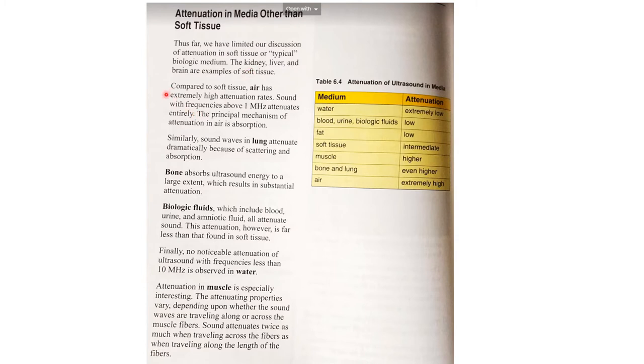Compared to soft tissue, air has an extremely high attenuation rate, and sound with frequencies above 1 megahertz attenuates entirely with distance. The principal mechanism of attenuation in the air is absorption. Similarly, in the lung, sound attenuates dramatically because of scattering and absorption, dealing with the way lungs are structured. Bone absorbs ultrasound energy to a large extent and results in substantial attenuation. Biologic fluid, which includes blood, urine, and amniotic fluid, all attenuate sound. The attenuation is far less than that found in soft tissue.